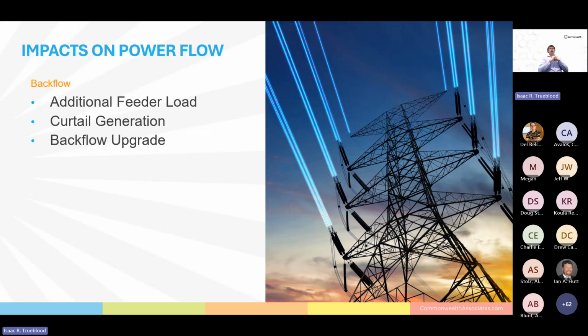This is, however, trickier than it sounds, as loads are not static. The load on a feeder increases and decreases based on months, days, or even hours. Was Monday a holiday? That may make Tuesday a greater load. However, there is a difference between a small few kilowatt distributed energy resource and a multi-megawatt distributed energy resource. There is a general rule that can be applied: if the distributed energy resource's capabilities are less than 20% of the feeder load, backflow conditions are considered unlikely. Now, I do want to stress that is not a hard rule, and any impact study should take more than just the 20% rule into account.